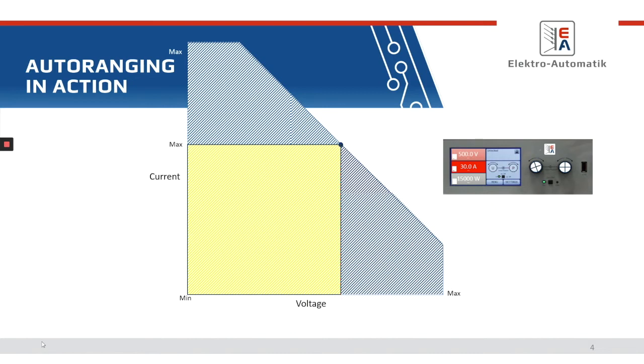So again, program down even further in voltage. Let's say you're down to that 250 volt mark, where we saw we were getting 7,500 watts from the other power supply. An auto-ranging power supply is going to increase its current to 60 amps. And again, you're still maintaining that full 15 kilowatts from the power supply.